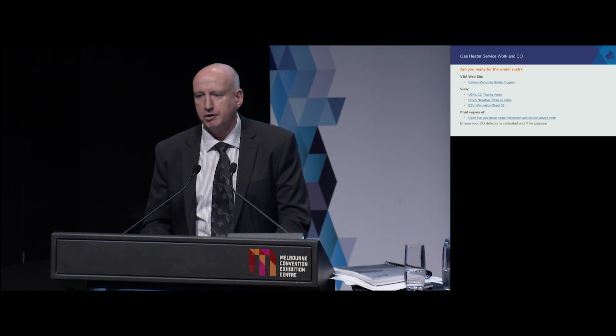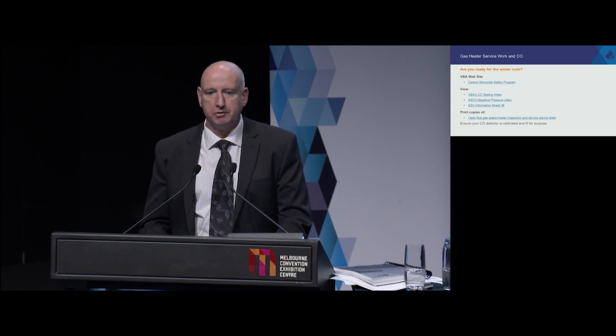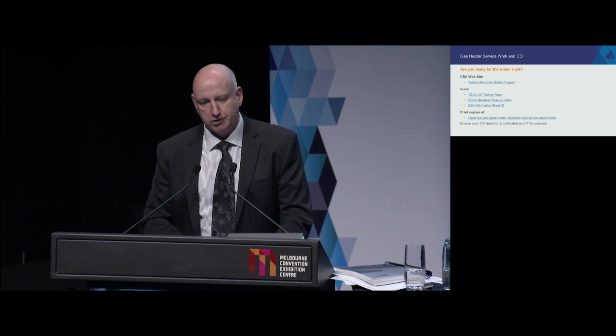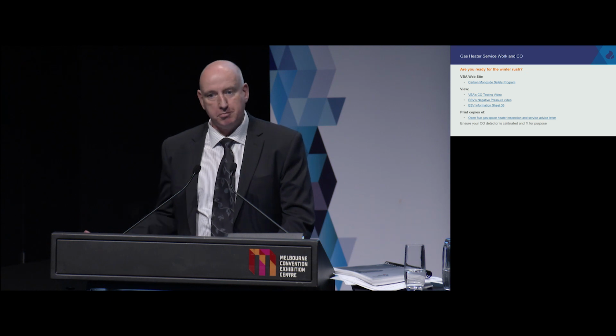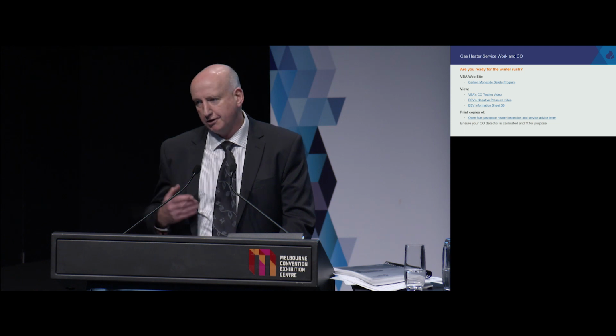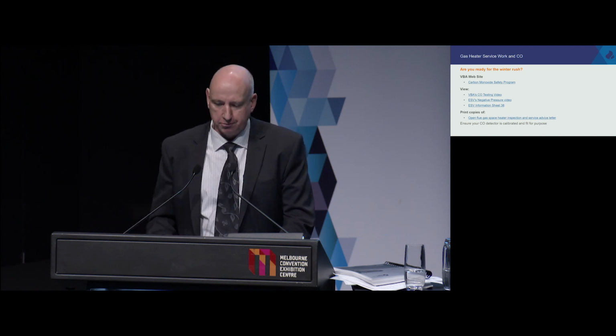So just be mindful that under a negative pressure environment, you are testing to see if that heater is spilling CO. There is a potential, so if it is, you need to stop your test immediately. You know, if the levels are going up, stop your test immediately, advise the consumer, establish why it is. It may be negative pressure, it may just be there's a fault with the heater, so then eliminate the negative pressure by turning fans off. And do the test again. If it's not spilling, then it was the negative pressure causing you the problem. That is all stepped out.